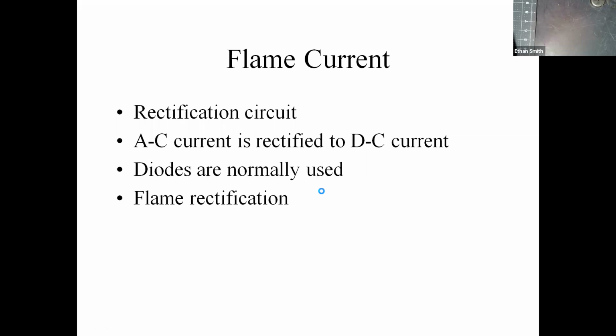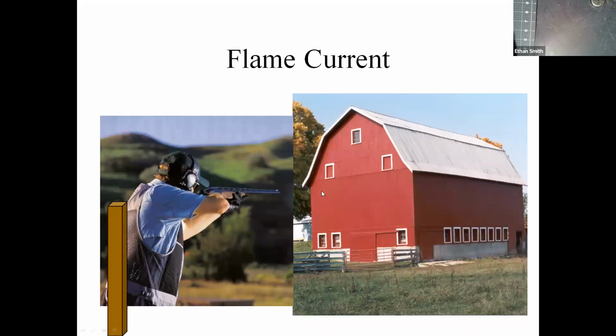Okay. And so if we equate this to a flame sensor, what we're trying to do is we've got our flame sensor over here. That's our post. And we've got a guy with a shotgun. So we're going to assume that this guy has a shotgun that shoots perfect circles of pellets, and he's only got pellets on the outer perimeter of this circle. So this is our shotgun that shoots rings of pellets. Okay, and what that simulates and what that equates to is the flame coming out of a burner.